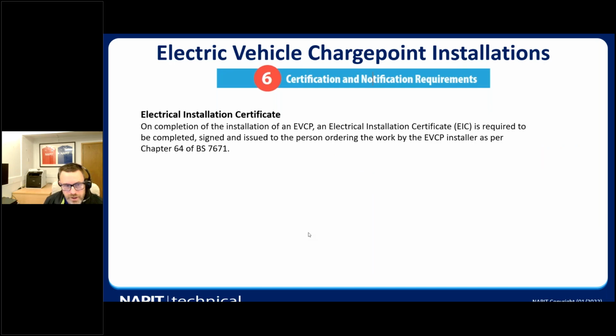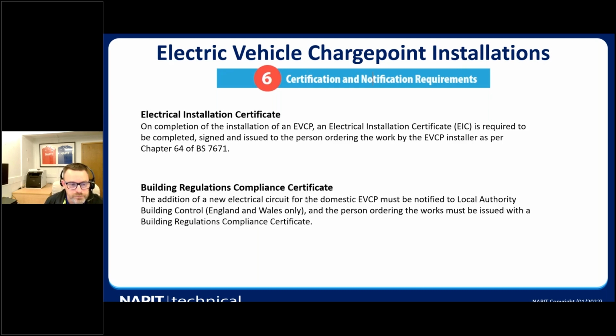And the electrical installation certificate has to be issued for an EV charge point. It's a new circuit, it's a new installation, so an electrical installation certificate must be issued for this, and has to be completed, signed and issued to the person ordering the work by the EV installer, as per Chapter 64 of BS 7671.